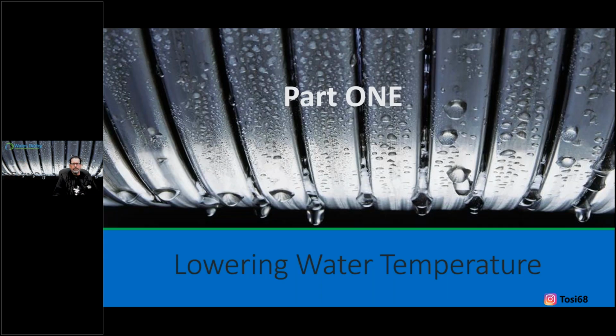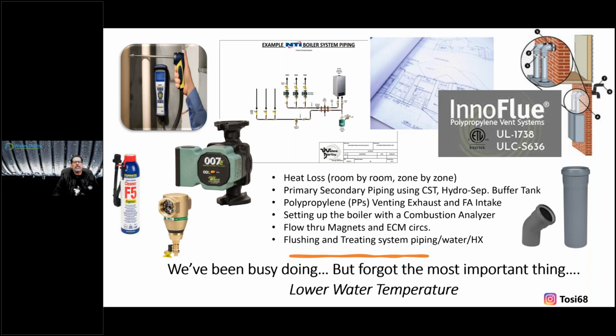Here's the title slide, part 1 of lowering water temperature. This really kind of changed the way I think about what I've been doing for the last 20 some odd years. First thing and foremost, first line item is heat loss. We have to start understanding envelope over equipment. The envelope of the building has to be the focus for what we're doing. Whether you're asking someone else to do it, or you're engaging and learning, or you've been doing it for a while, there is no better step in the right direction than doing a heat loss, room by room, envelope of the building, zone by zone, however you want to approach it. That tells you exactly what the equipment then needs to be sized as. So you'll see later the bigger isn't always better approach.